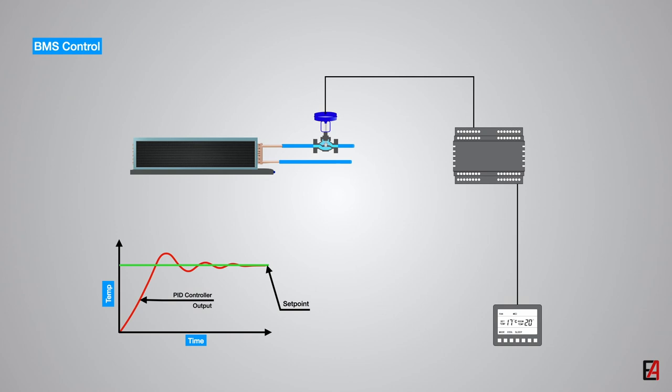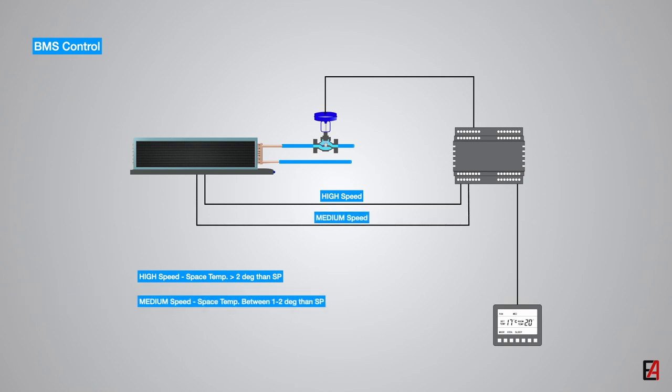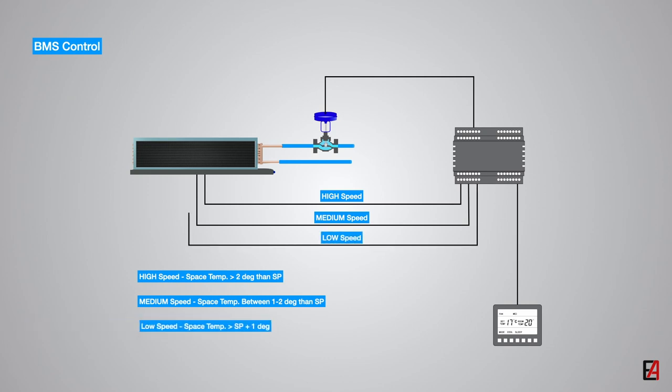The optimum fan speed control of FCU can be achieved with the following configuration. When the temperature difference between the space temperature and the setpoint is more than 2 degrees Celsius, the fan can be set to run at high speed. When the temperature difference is between 1 to 2 degrees Celsius, then the fan shall run at medium speed, and when the temperature difference is between 0 to 1 degrees Celsius, then the fan coil unit shall run at low speed and continue to run at low speed even after achieving the setpoint.